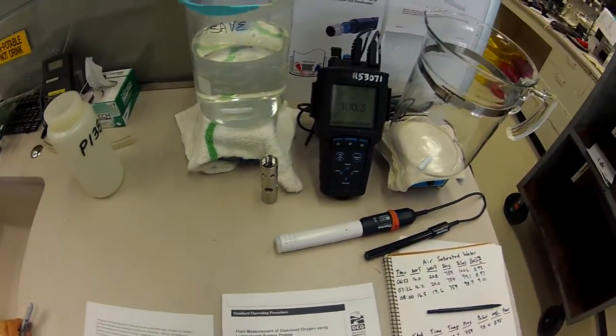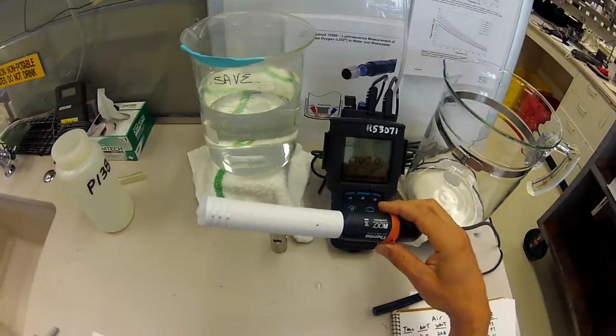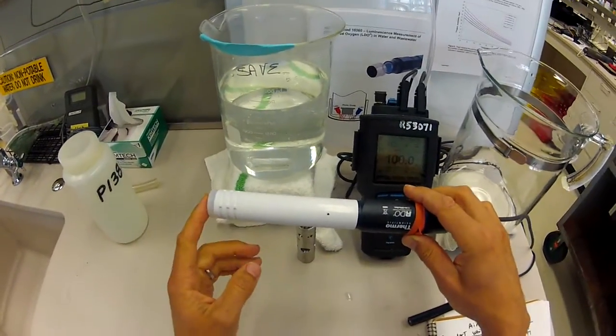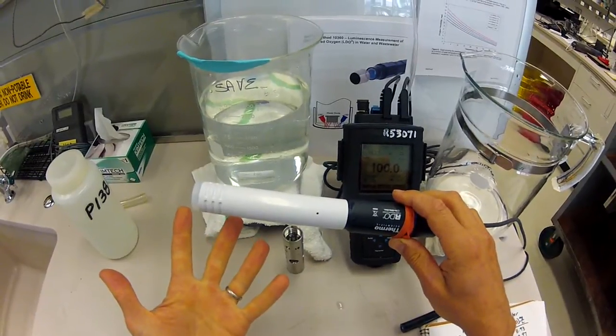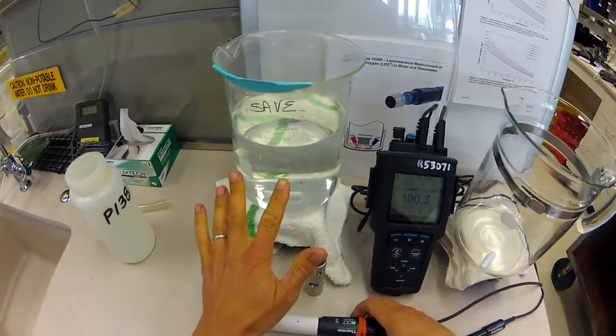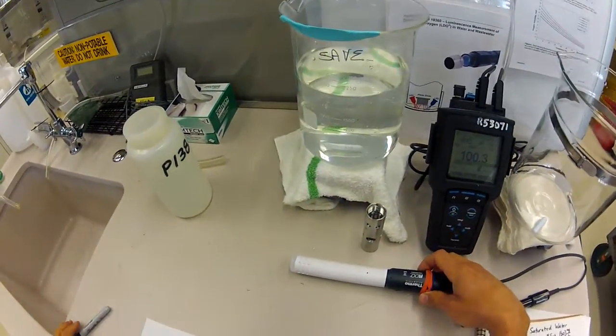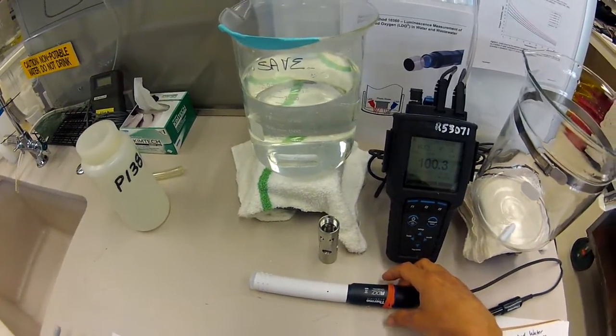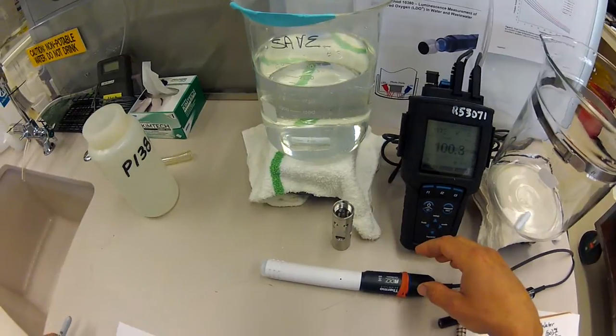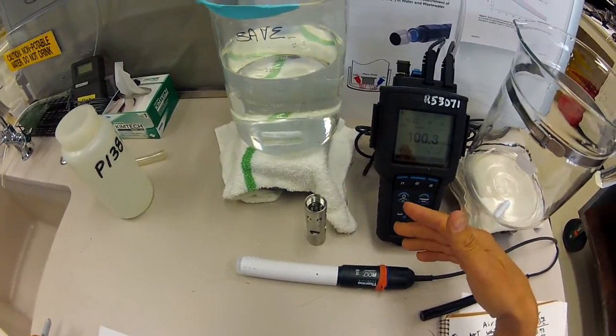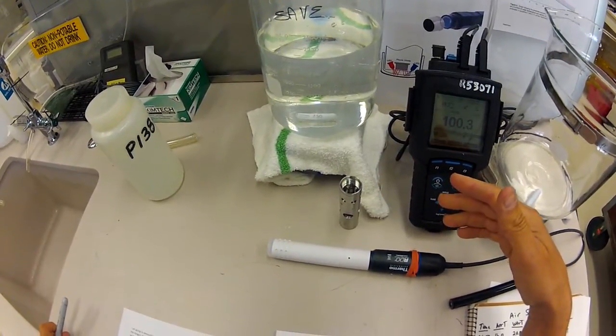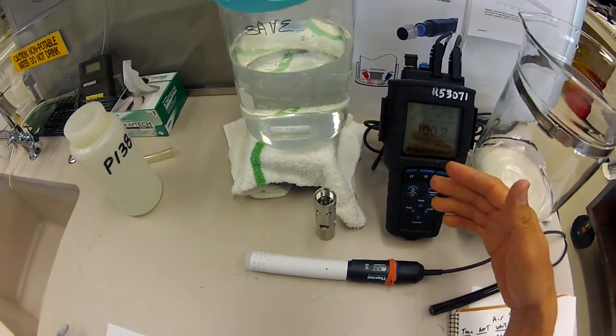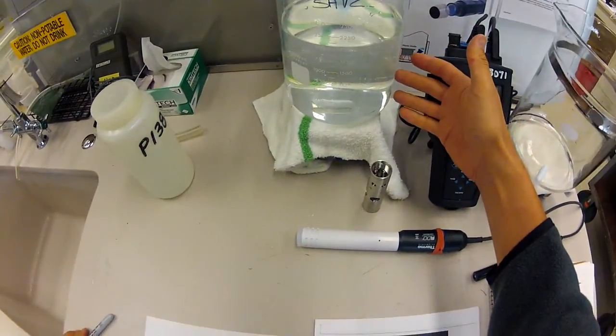Similar to when we did a DO meter calibration where we saturated air with water, we're now just going to flip that and take water and saturate it with air. We're going to need stable temperature and barometric pressure conditions in order to reach equilibrium between the air and the water.